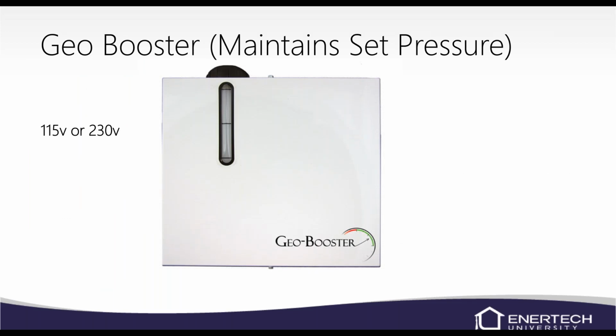Geo Booster: if you're dropping pressure and you're out there a couple times a year to boost it back up, more than likely it's got a small leak somewhere. It's one thing if you can look in a basement or crawl space for some pipe that's leaking, but if it's not leaking anywhere you can get to it, it's in the ground somewhere, so it's not like you're going to dig up that ground and try to find it. It's not going to happen. Obviously, if it's a huge leak, you've got to do something about it.